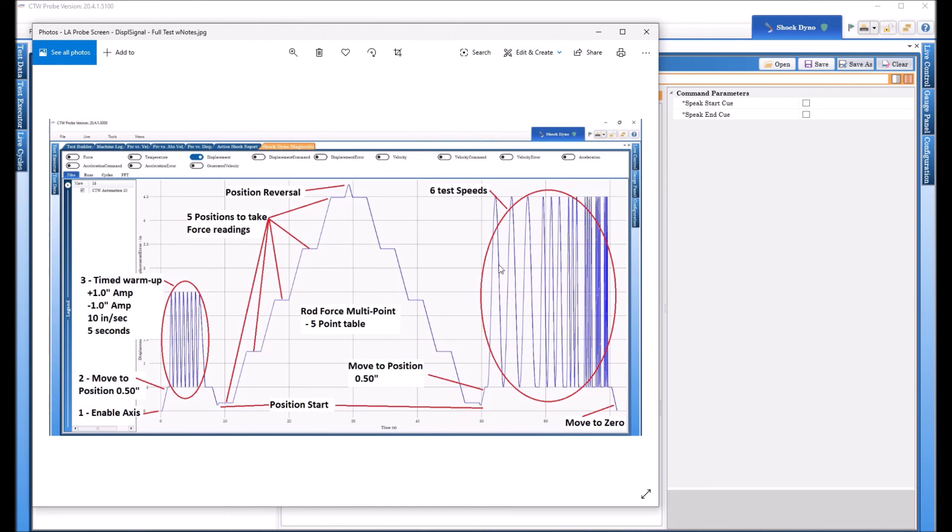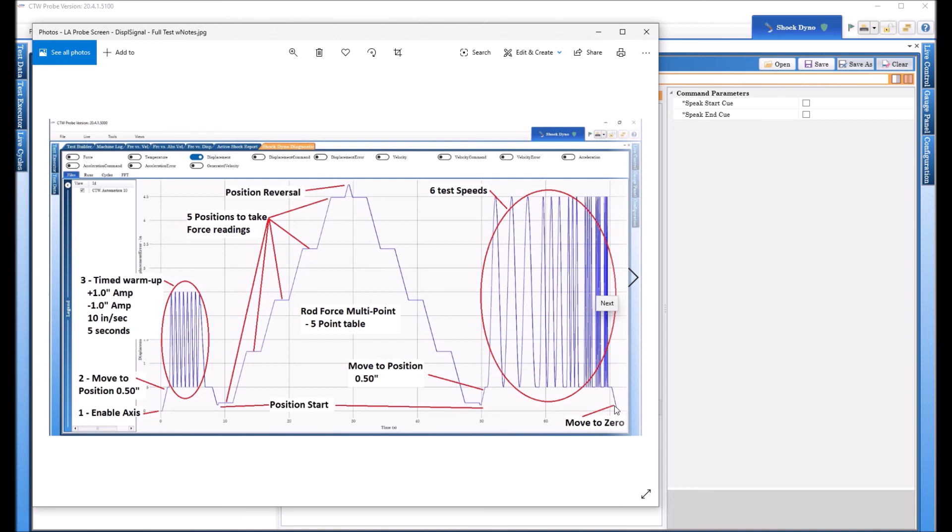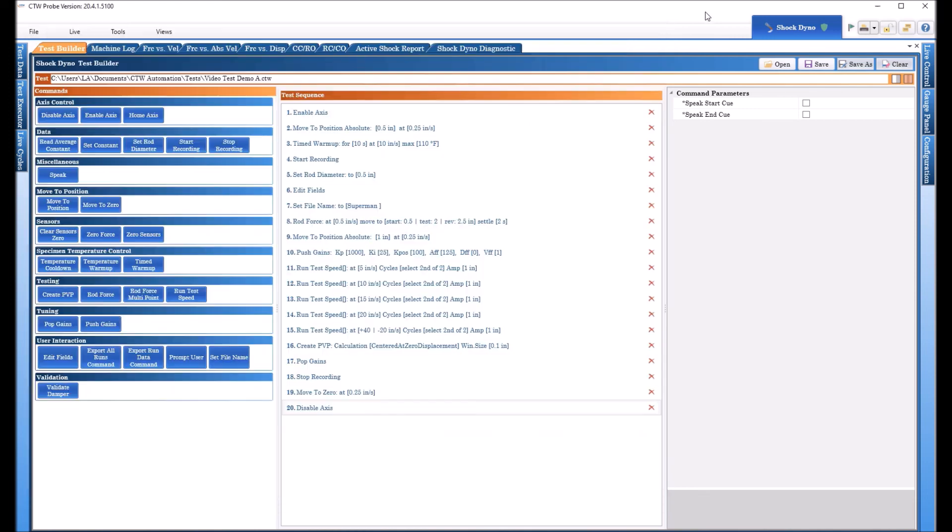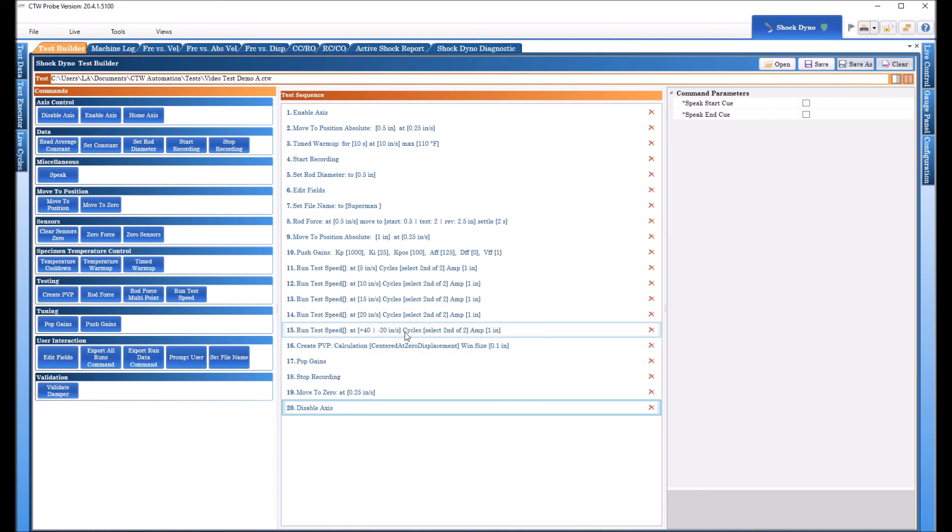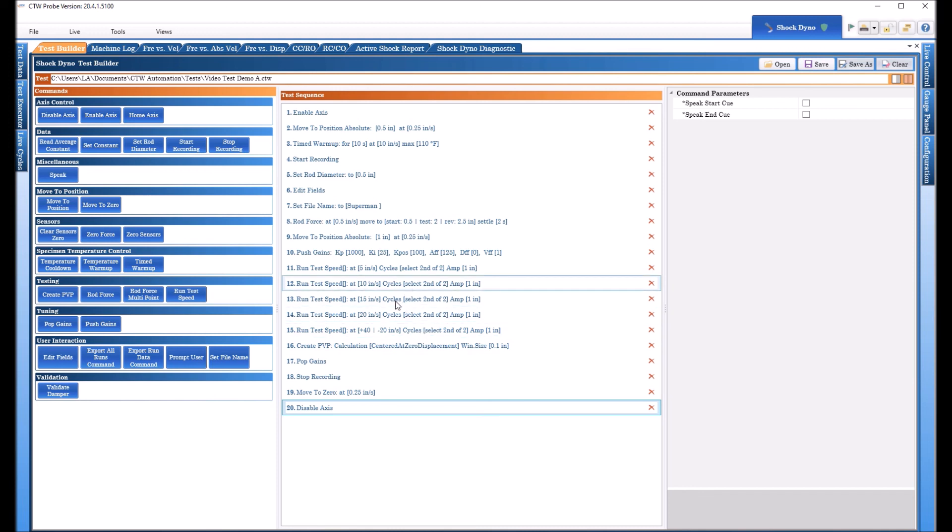And this is the displacement sensor so this is the displacement so you can see we ran one speed another speed another speed you can see they're getting smaller and smaller that means it's getting faster and faster. So it ran all those speeds it created the PVP and we moved it back home we turned it off. So that's what an actual test would look like if you could see the displacement. So there is your second step your second video course in doing the linear actuator test sequence and we're going to make another one and we're going to go through the rod force multi-point. So there you go see you later.